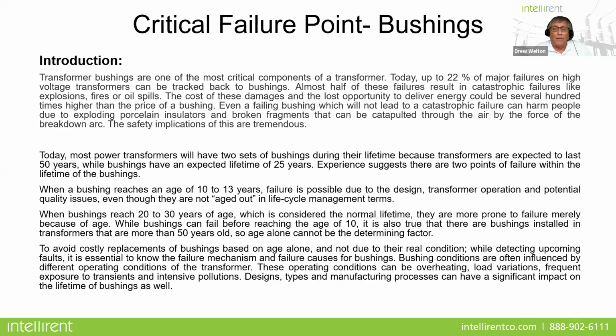But our experience suggests that there really are 2 points of failure within a lifetime of the bushings. So when a bushing, let's say, reaches age 10 to 13 years, failure at that point can be possible due to either design of the bushing itself or how the transformer is operating and potential quality issues, even though they're not aged out in terms of life cycle management. But when a bushing reaches 20 to 30 years of age, and that's considered the normal lifetime, they're more prone to failure merely because of age.